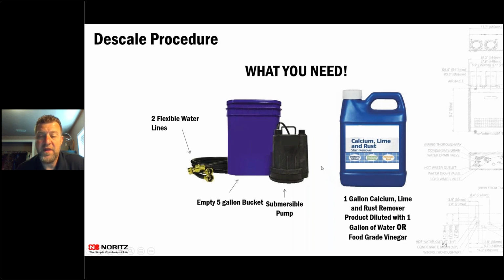So when you are descaling that unit, the things you would need are washing machine hoses, a 5-gallon bucket, and a submersible pump. I've seen guys use transfer pumps too. If you're using CLR, the calcium lime rust stain remover, dilute it with a gallon of water, a 50-50 mix, or food grade vinegar works great. If you have a unit that is regularly being flushed, food grade vinegar will work just fine.